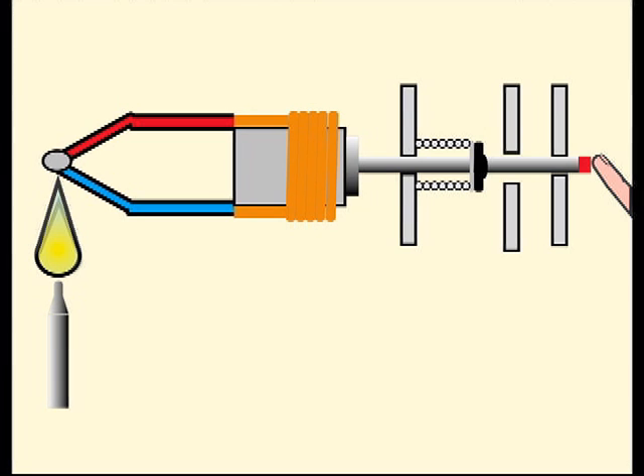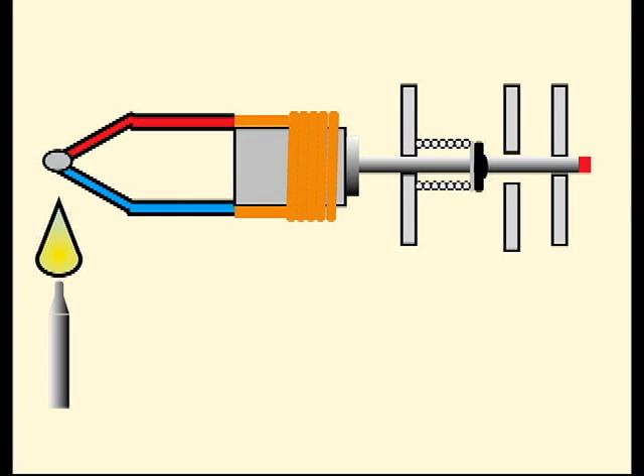If we now release the start button, the magnetization of the core does not allow the spring to pull the iron plate. While the thermocouple is hot, the ferromagnetic core will be magnetized and the spring cannot pull the iron plate away from the core, thus opening the gas flow so the heater can work.